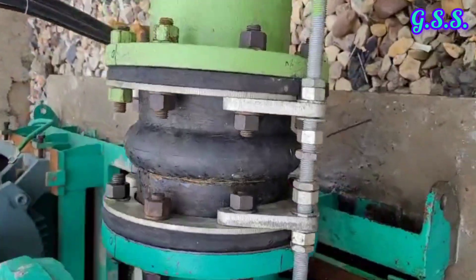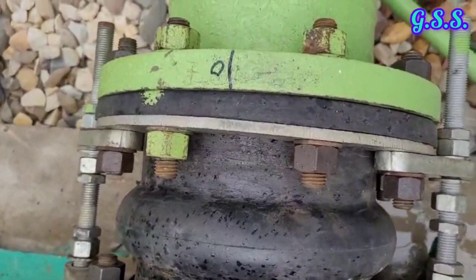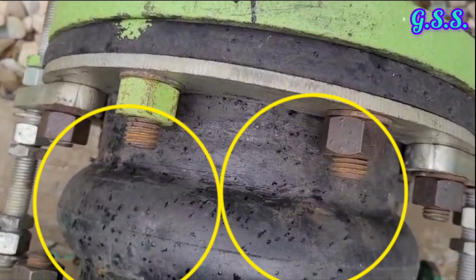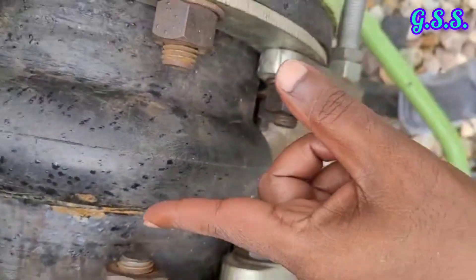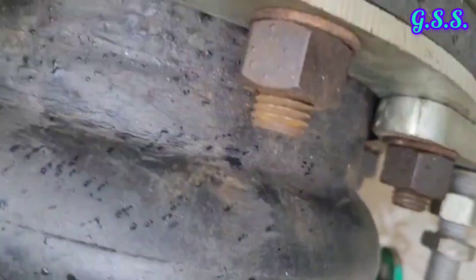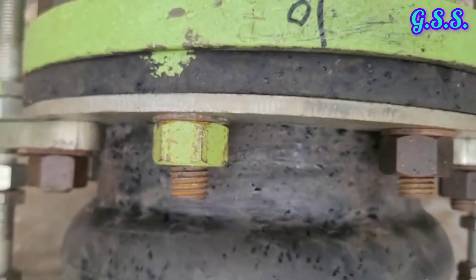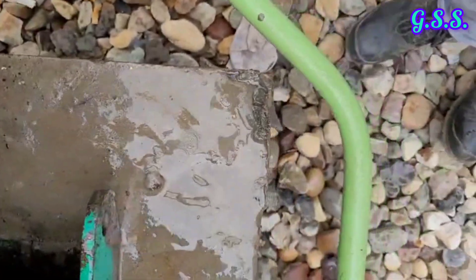Now you can see the discharge side bellow. You can see several small pitting holes on the bellow surfaces. Also you can see a crack at the bellow arch starting area, including at the bottom surface area.